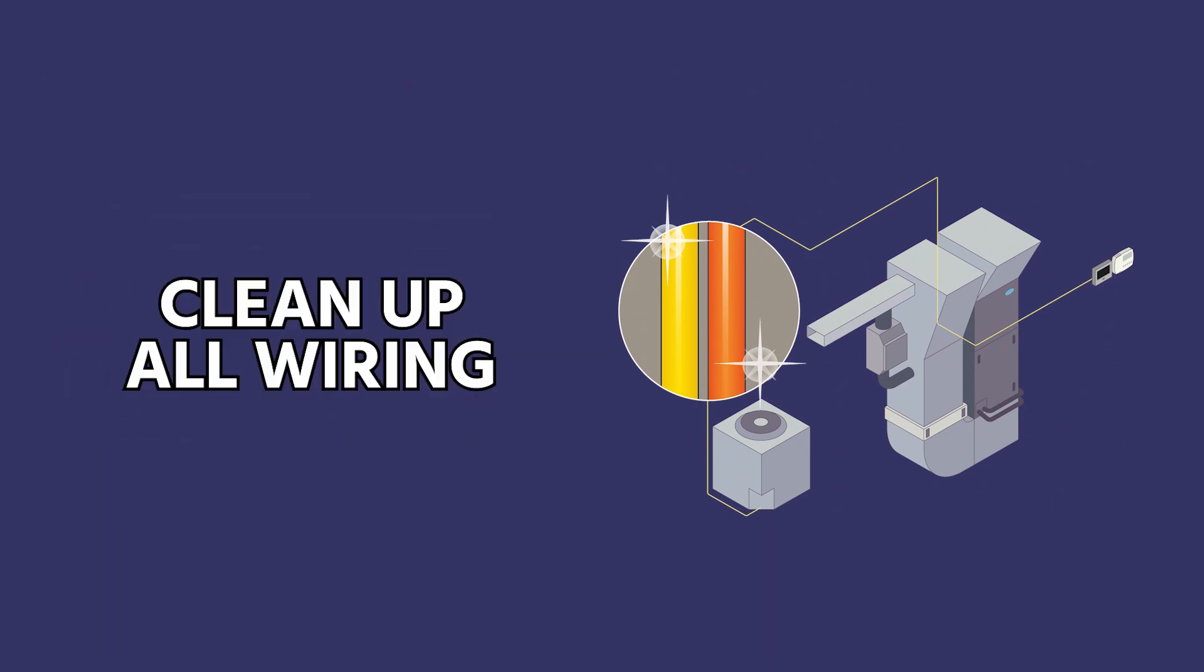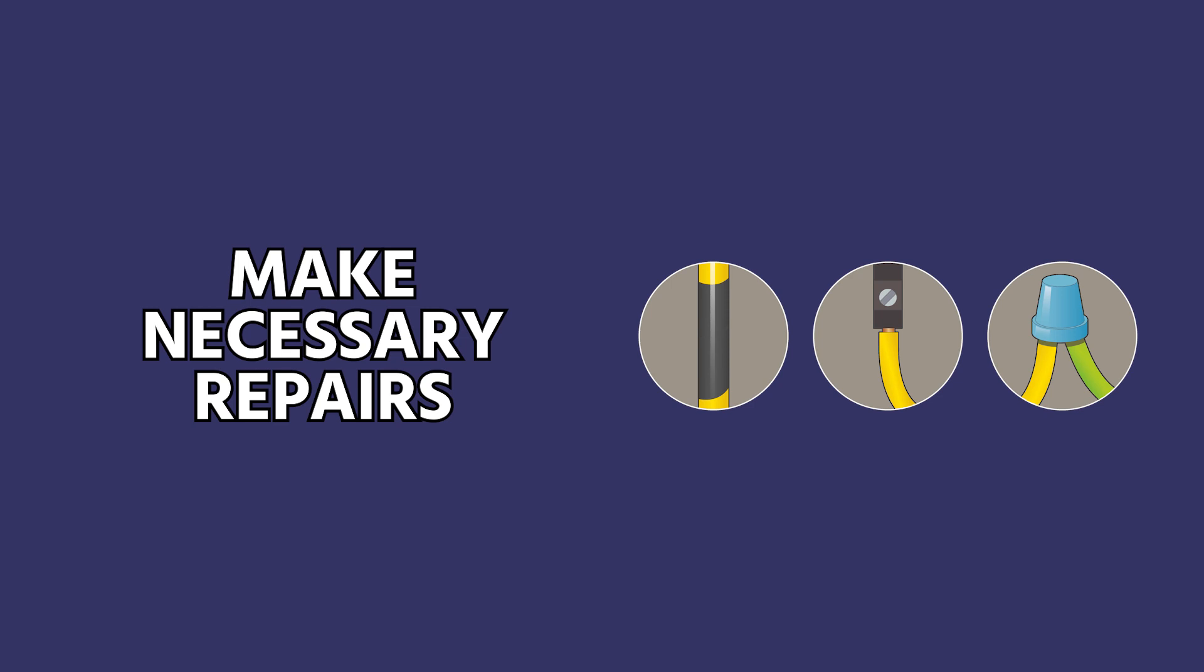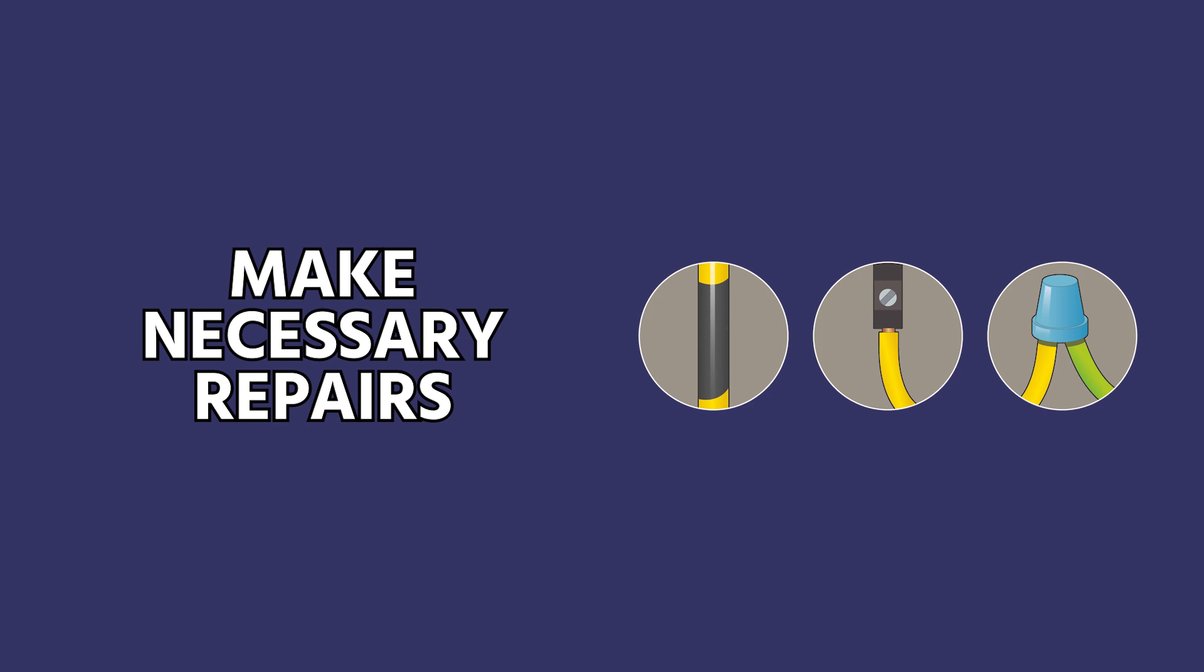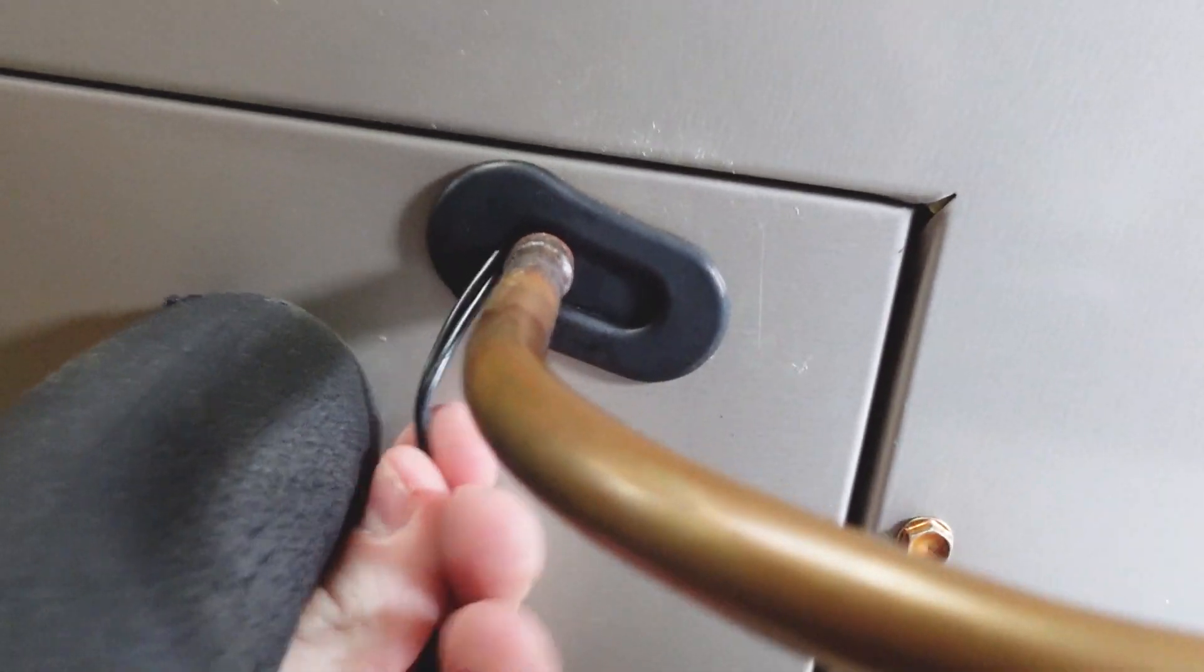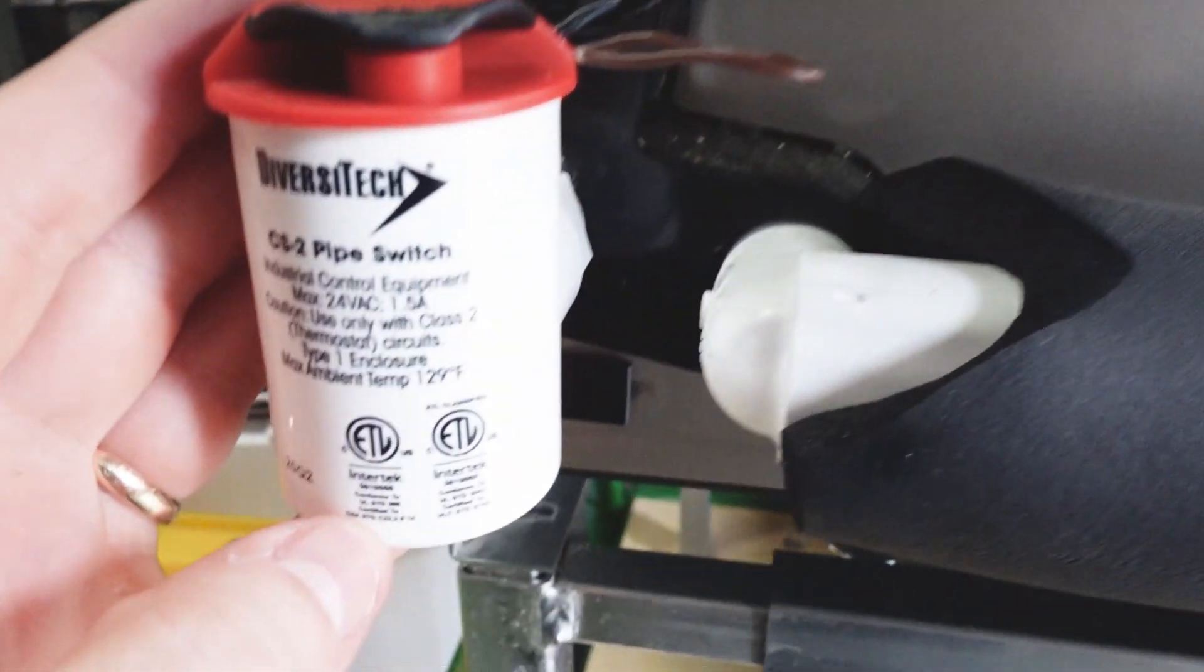In general, we would want to clean up all the wiring and make it look neat and find anything that could have caused this problem before we go ahead and put a new fuse in. Check your float switch wires. Make sure there's no damage to any of those. Maybe they could be chafing up against some tubing if they're routed improperly.